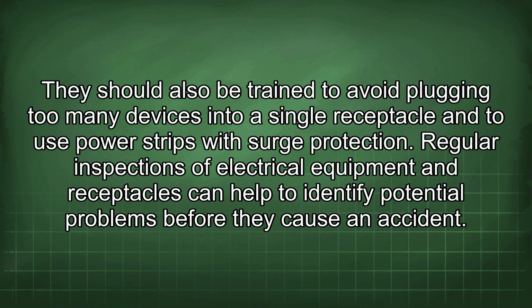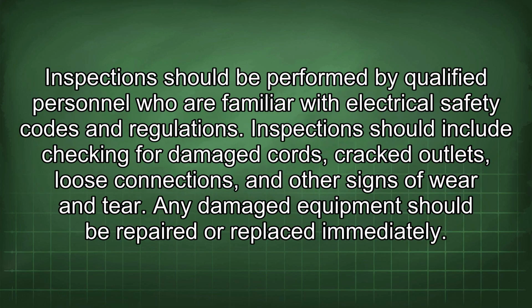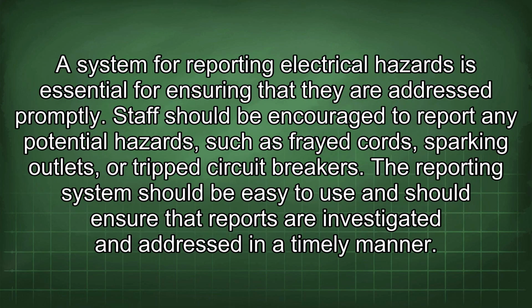Regular inspections of electrical equipment and receptacles can help to identify potential problems before they cause an accident. Inspections should be performed by qualified personnel who are familiar with electrical safety codes and regulations. Inspection should include checking for damaged cords, cracked outlets, loose connections, and other signs of wear and tear. Any damaged equipment should be repaired or replaced immediately. A system for reporting electrical hazards is essential for ensuring that they are addressed promptly. Staff should be encouraged to report any potential hazards, such as frayed cords, sparking outlets, or tripped circuit breakers.